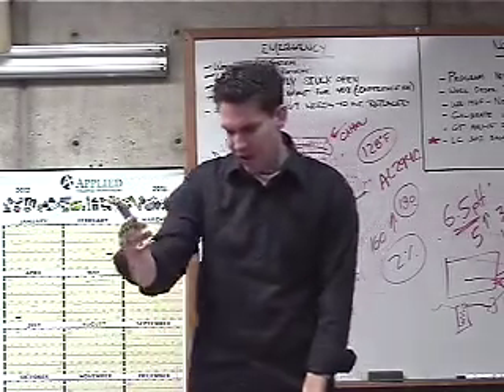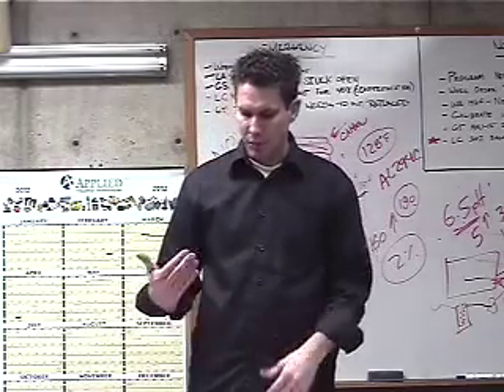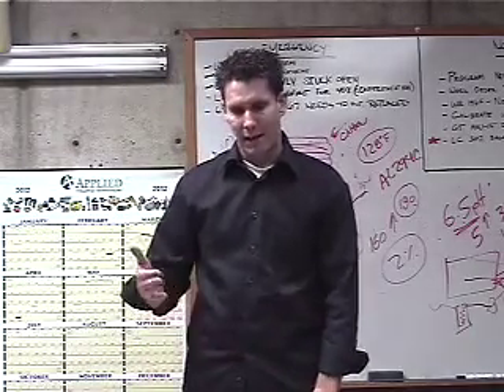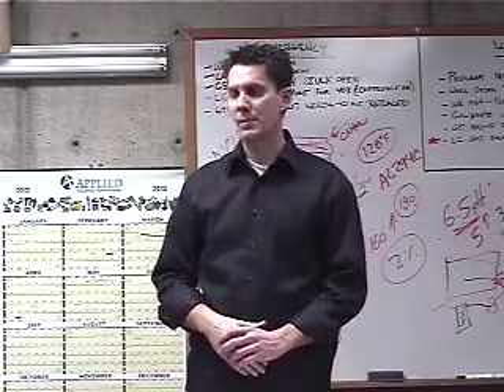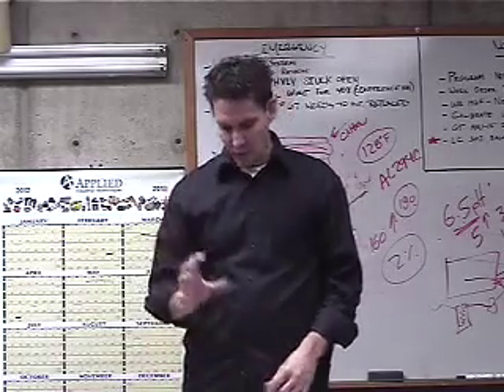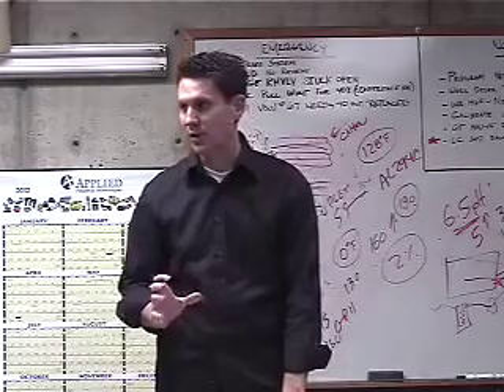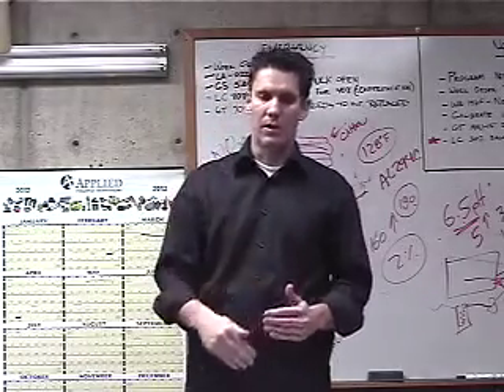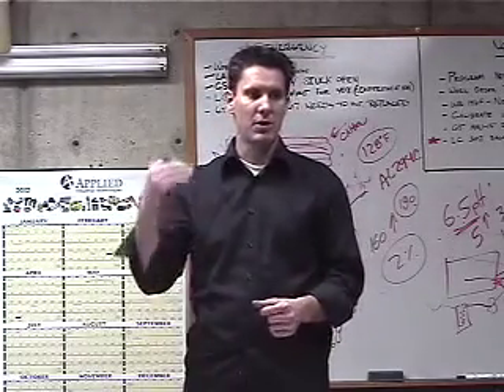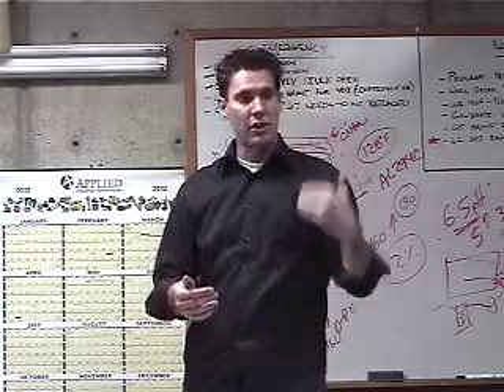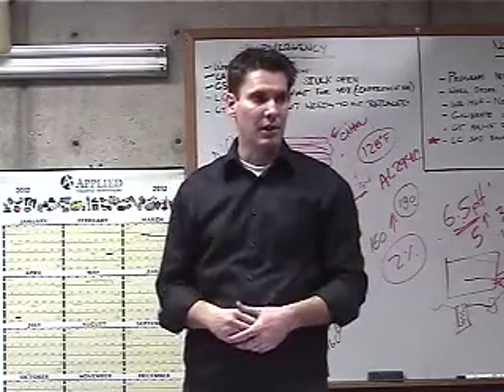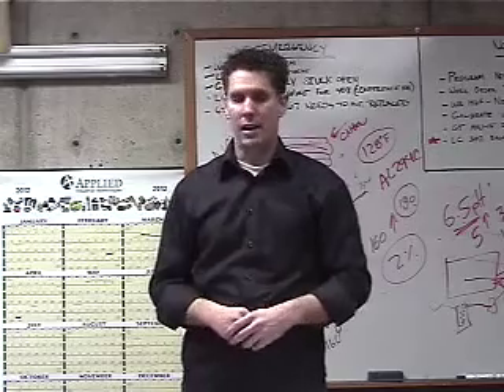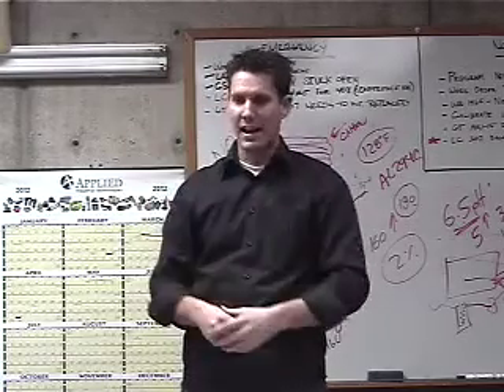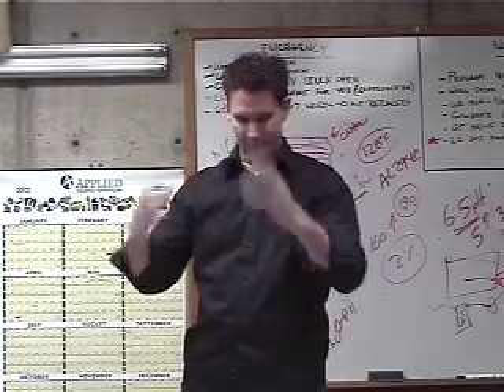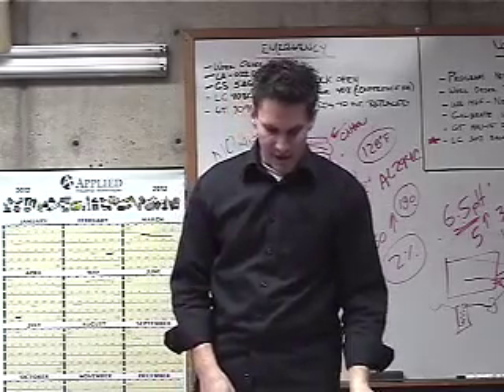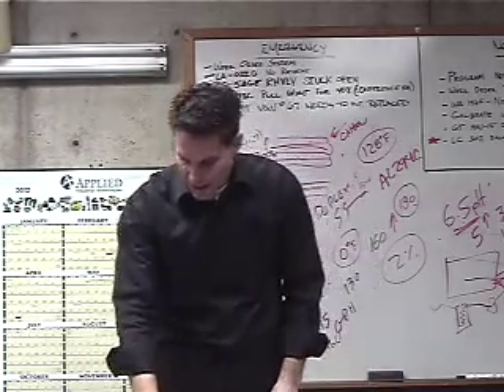Troubleshooting. One of the things they wanted us to talk about were some typical problems that we see with these boilers. Again, I'll stress, the most typical problem we see is poor combustion. So that's why in this manual, in the maintenance instructions, it's going to keep repeating over and over, check for blockage in the flue. Make sure there's nothing obstructing the combustion air inlet and the exhaust leaving the building. A simple bird's nest in the combustion, I see that all the time. Some type of nesting that gets put in there. So these are things you want to watch out for.